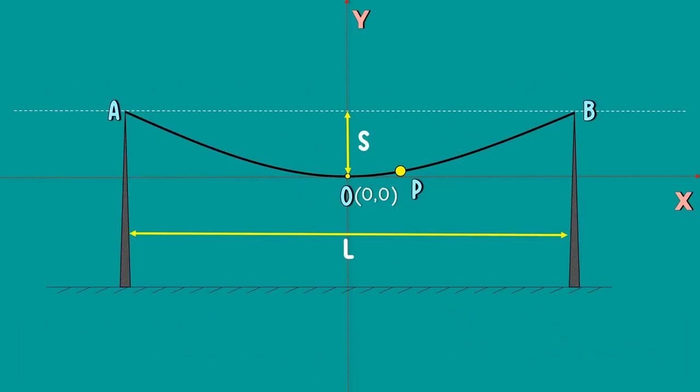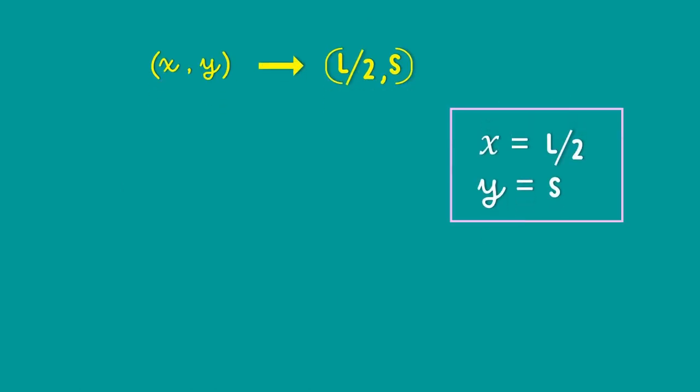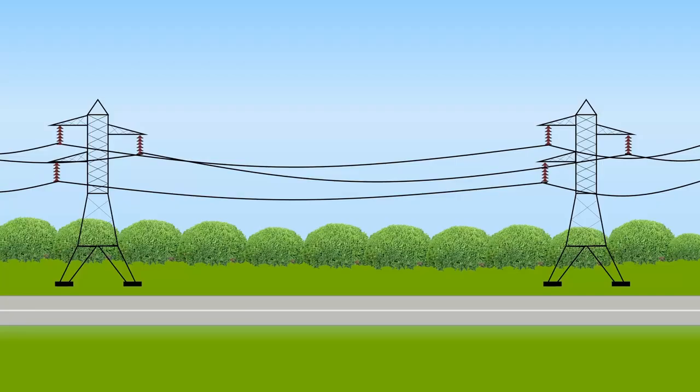Now, if we extend our point P to point B, then the coordinates X and Y will be L by 2 and S. Here, S represents the sag. So if we substitute these X and Y values in our equation, we will get our sag equation. S equals WL squared divided by 8T. This sag equation is applicable only when the supports are at an equal level.